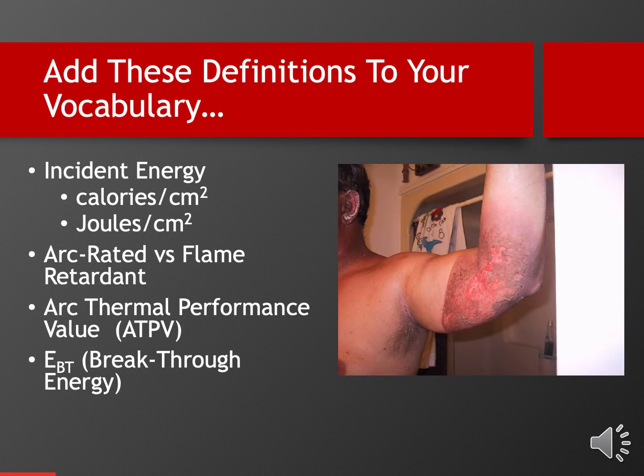Some definitions to add to your vocabulary. Well, of course, incident energy is one of the most important definitions, and incident energy is measured in 2 ways. Here in the U.S., it's measured in calories per square centimeter, and more in Europe, it's measured in joules per square centimeter, which is more of a mechanical part of the discussion. In the U.S., the magic number for the number of calories per square centimeter we're interested in is 1.2 calories. 1.2 calories per square centimeter of your skin will render you a 2nd-degree burn.